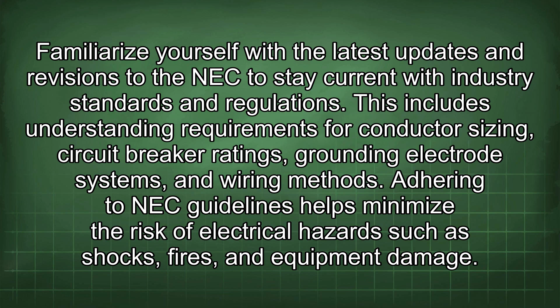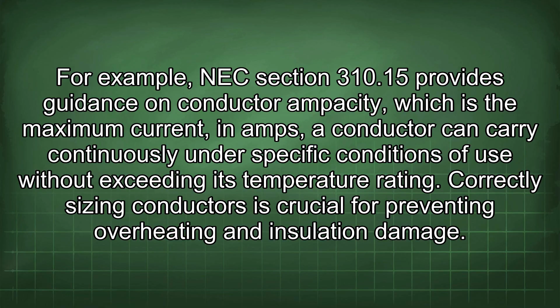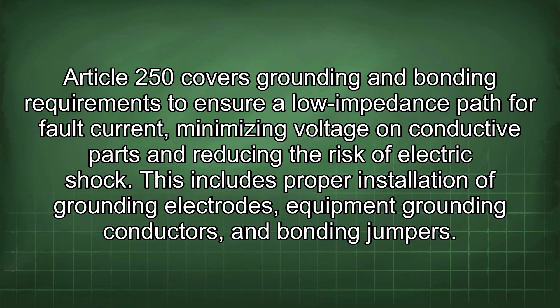For example, NEC Section 310.15 provides guidance on conductor ampacity, which is the maximum current, in amps, a conductor can carry continuously under specific conditions of use without exceeding its temperature rating. Correctly sizing conductors is crucial for preventing overheating and insulation damage. Article 250 covers grounding and bonding requirements to ensure a low impedance path for fault current, minimizing voltage on conductive parts and reducing the risk of electric shock. This includes proper installation of grounding electrodes, equipment grounding conductors, and bonding jumpers.